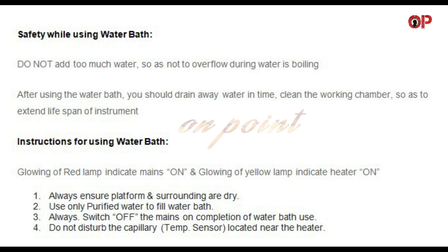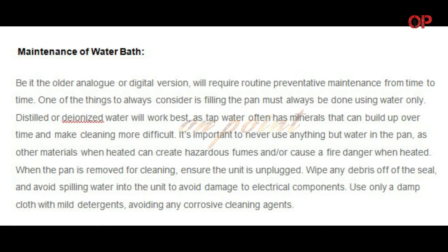Instructions for Using Water Bath: Glowing of Red Lamp indicates Mains On, and glowing of Yellow Lamp indicates Heater On. Always ensure the platform and surrounding area are dry. Use only purified water to fill the water bath. Always switch off the Mains on completion of water bath use. Do not disturb the Capillary Temp Sensor located near the Heater.